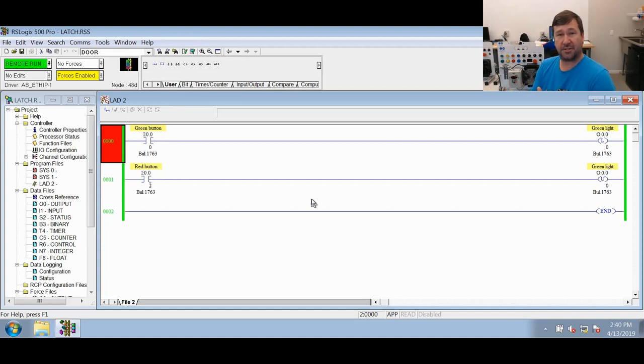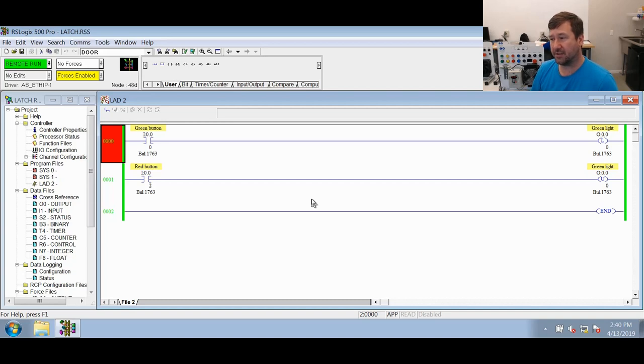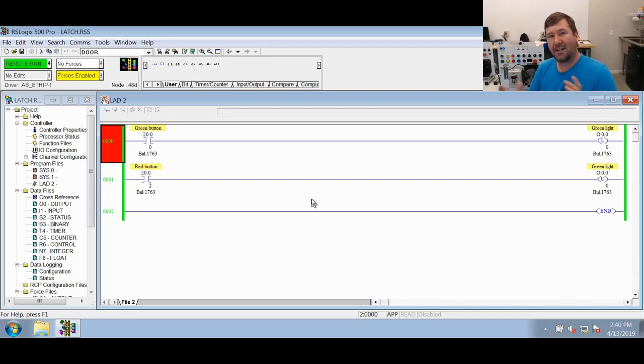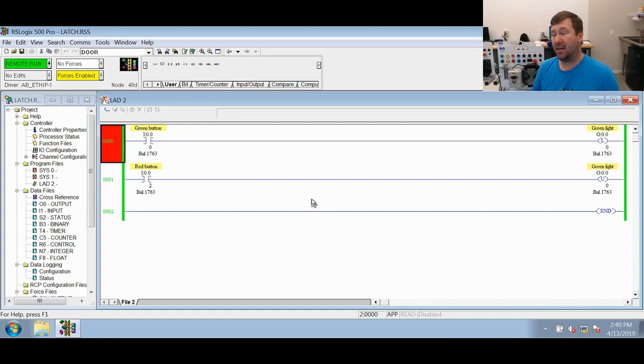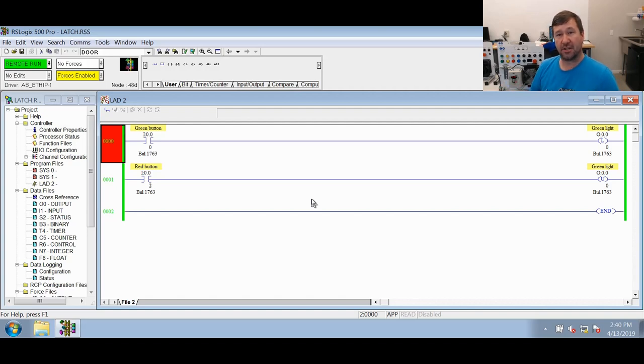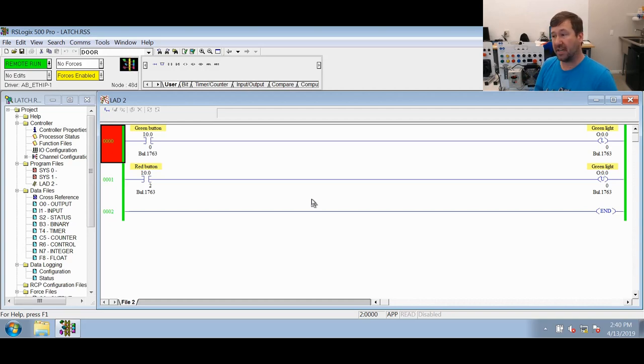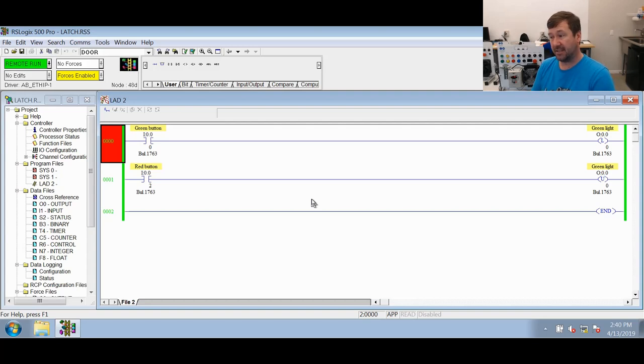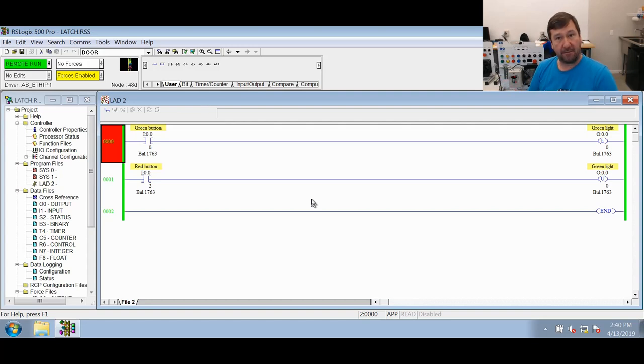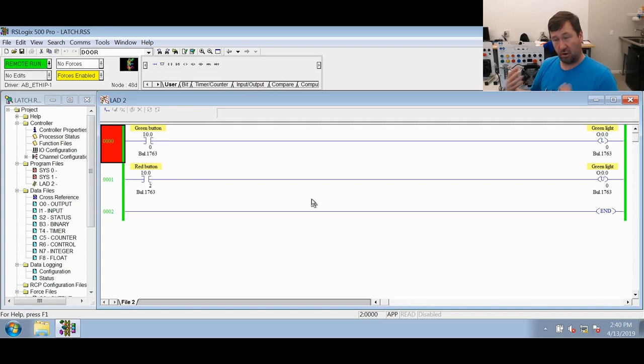The latch instruction is one of those that's fairly misunderstood as to what actually is latching this bit. If we go back to our basic OTE instruction, you'll remember that it executes based on whether it is true or false coming in. So a true OTE says go write a one to whatever address is in it. A false OTE says go write a zero.